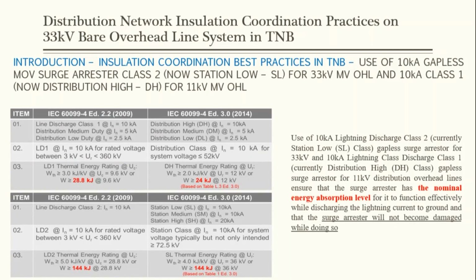So it has to work over time, right? It has to discharge so many times before the core of the lightning arrestor or the surge arrestor becomes hot, right? So if it is unable to absorb that kind of energy, it will damage the surge arrestor. So we have to have a higher energy absorption level with the system we have in Malaysia. Why? Again, because we have one of the highest GFD in the world.